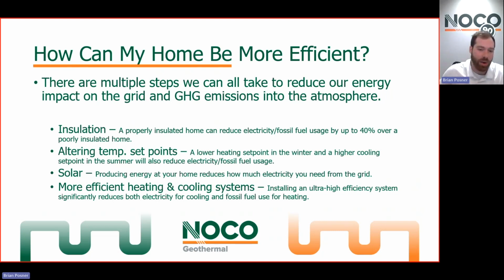Instead of pushing hot air from a home into 80, 90 degree summer air with an air conditioner and air source system, we are pushing it into the 50 some degree ground. Instead of having to force that hot air to accept more heat, we're letting the earth naturally pull the heat out of our homes because it's 50 some degrees. It's more than happy to absorb the high 60s, the low 70s, maybe even the low 80s, the heat that's coming out of your home. Well, it's at a lower temperature. It'll naturally pull that heat out. All we have to do is move that heat with refrigerant. So geothermal systems in a nutshell are letting the earth do our heat exchange for us and saving us vast amounts of energy.